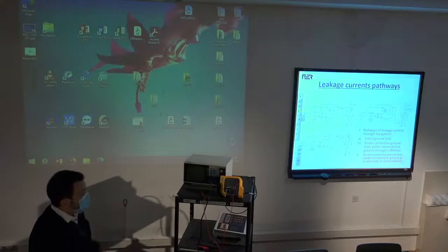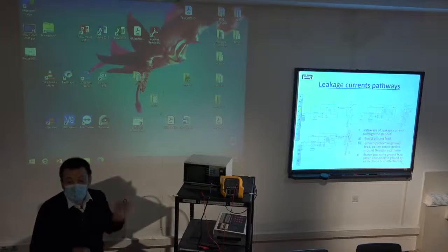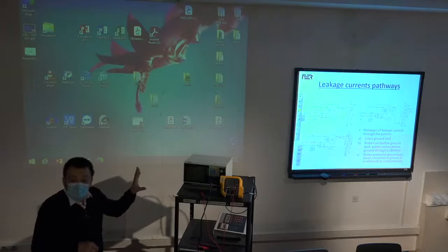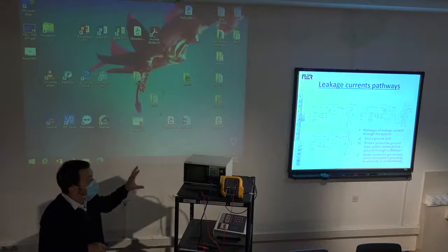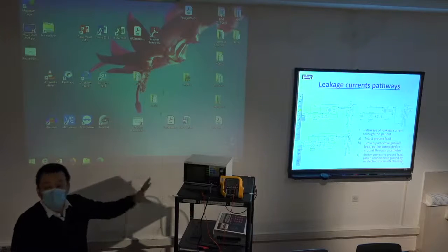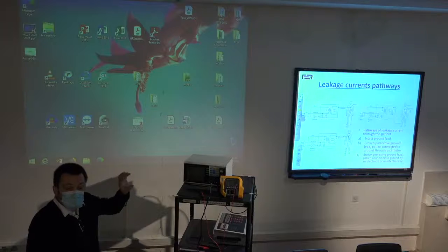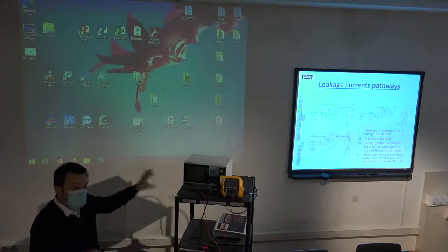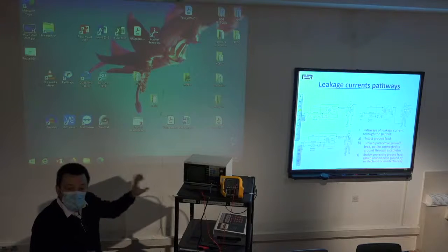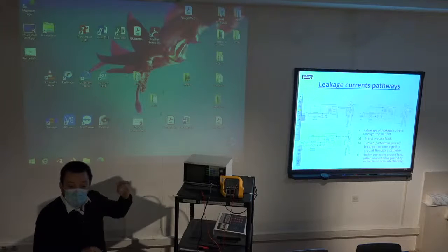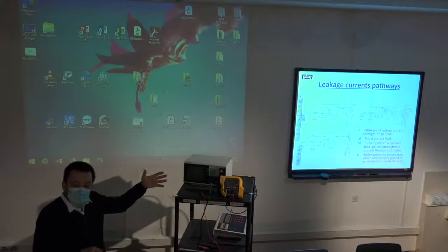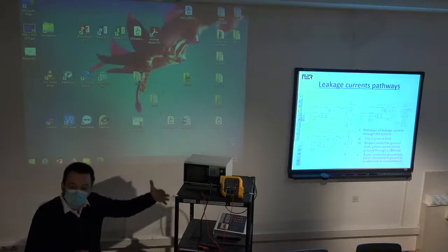So as I said, the small device that you can see here is actually devoted to measuring all the possible situations and all to see what kind of currents may be leaking through different parts of the device. Because if you remember, I told you that in many medical devices you have somewhere the isolation circuit.